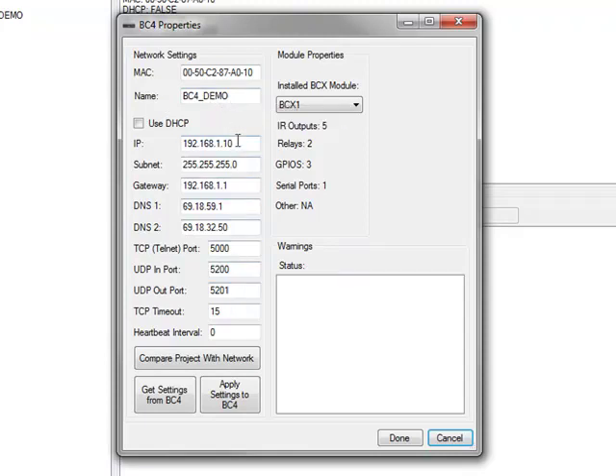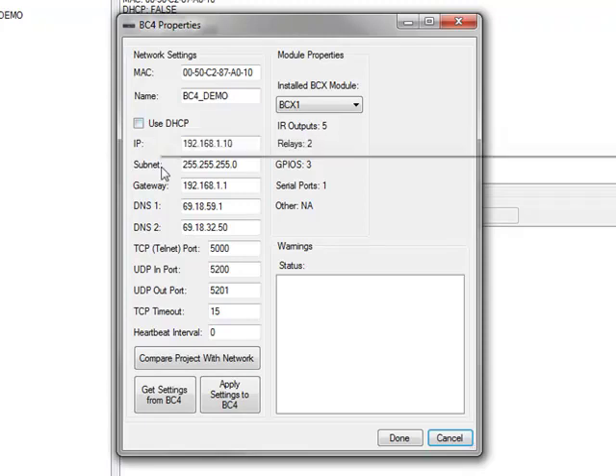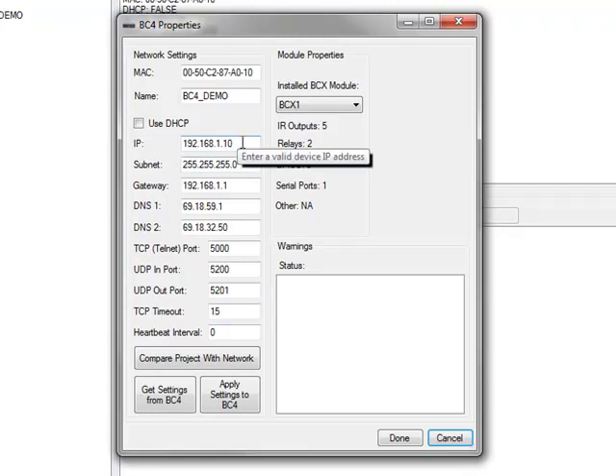If you haven't done so already, it's a good idea to give this BC4 a static IP address that's outside the range of your router's DHCP settings. To do that, just uncheck the DHCP box and give it whatever IP address you'd like. That way, if the BC4 is power-cycled, it's still going to come back to a known IP address, and any other systems on the network that are communicating with it know how to find it.